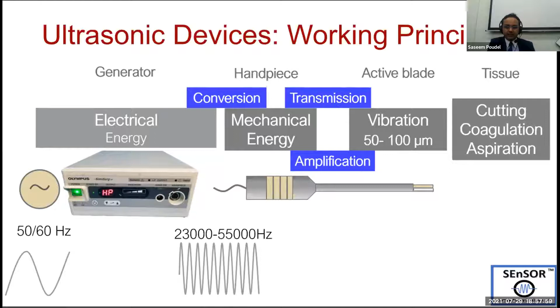In simple summary, it causes a few effects. Because there is vibration, it causes friction and heating. Heat is one of the obvious things that happens, because there is friction between the active blade and the tissue pad. This heat causes a tissue effect similar to monopolar coagulation.